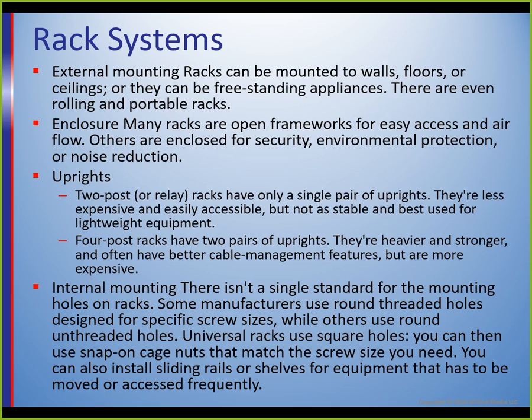And internal mounting. There's no single standard for the holes, and usually you're going to get one that has a lot of different holes, depending on what device you're putting in it and where you can mount it securely. Some use rounded threaded holes designed for specific size screws. Others use round unthreaded holes, different requirements from different vendors. Typically there are sliding rails to pull the equipment out for maintenance so you can work on it and put it into the rack, kind of like a kitchen drawer you pull out.